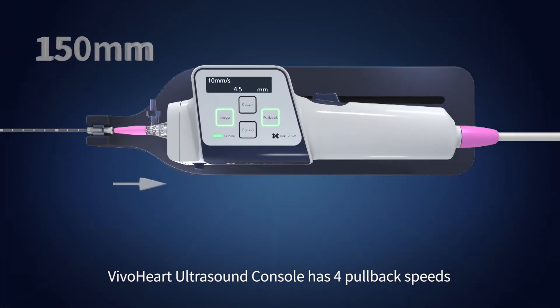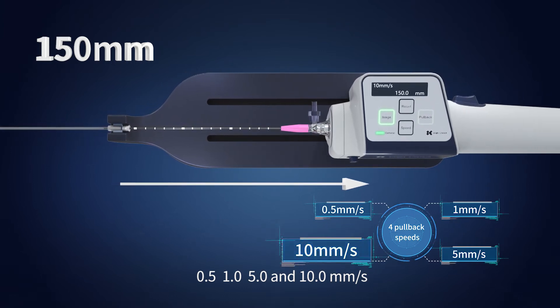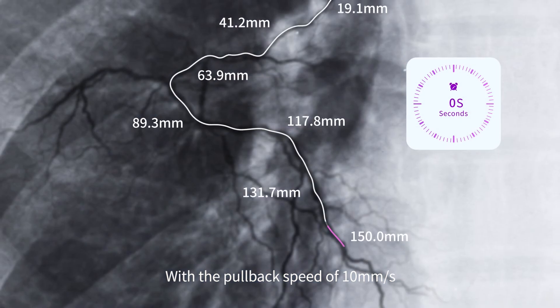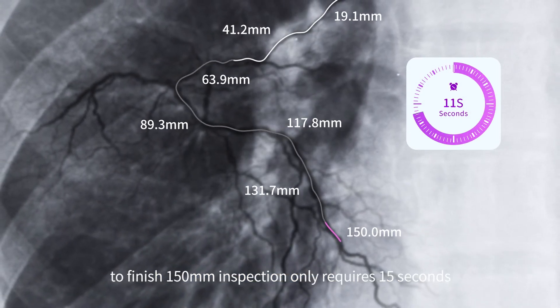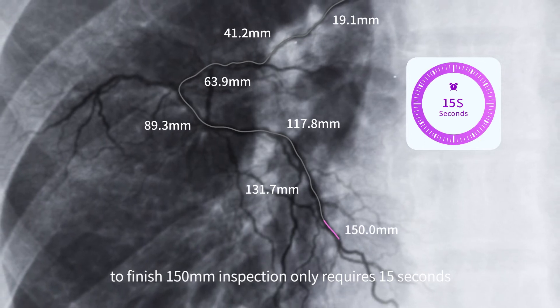The Vivo Heart Ultrasound console has four pullback speeds: 0.5, 1.0, 5.0, and 10 millimeters per second. With a pullback speed of 10 millimeters per second, finishing a 150-millimeter inspection only requires 15 seconds.